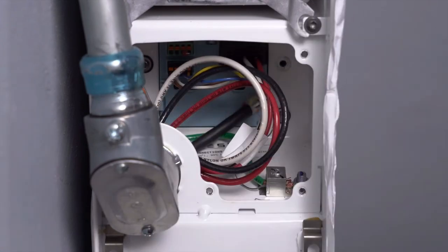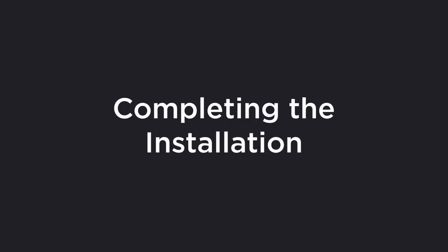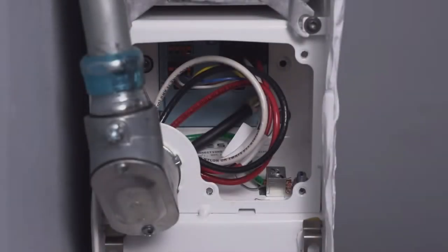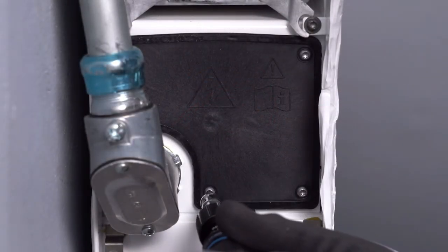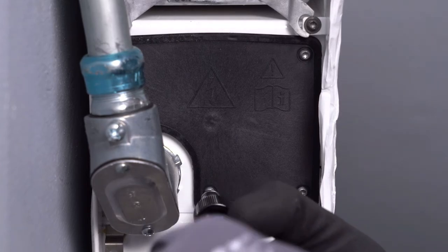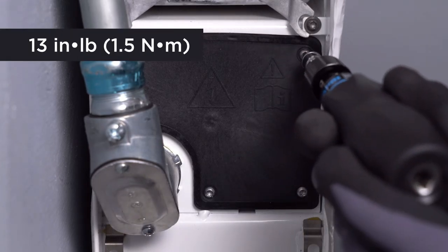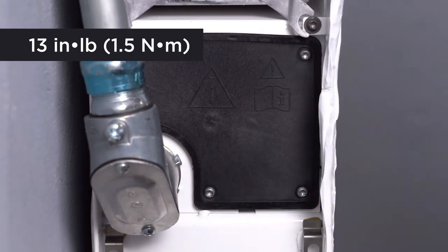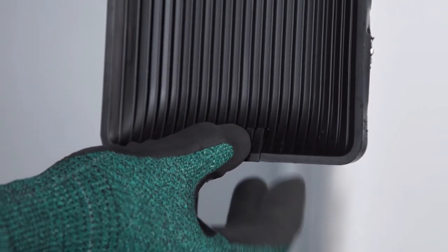Neatly pack the wires and connectors into the wiring compartment. Install the cover on the Powerwall 2 wiring compartment. Tighten the fasteners with a T20 Torx bit to a torque of 13 inch-pounds.